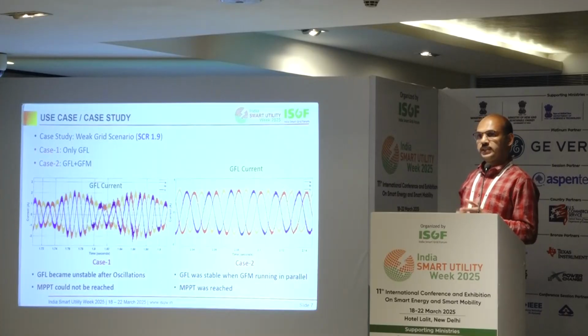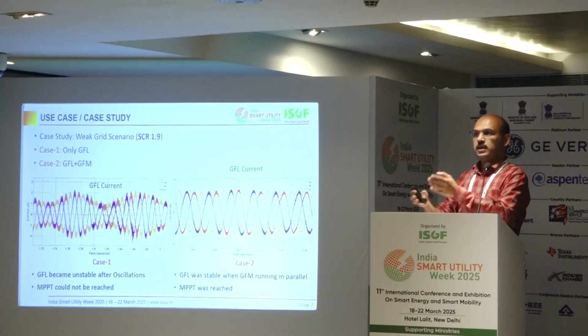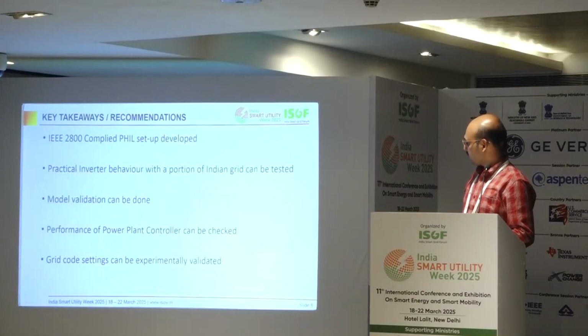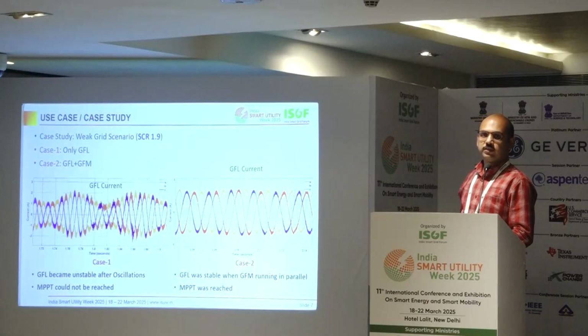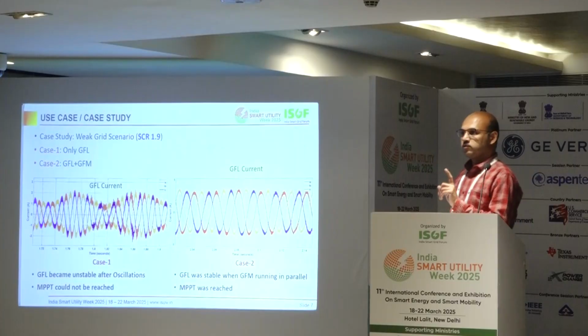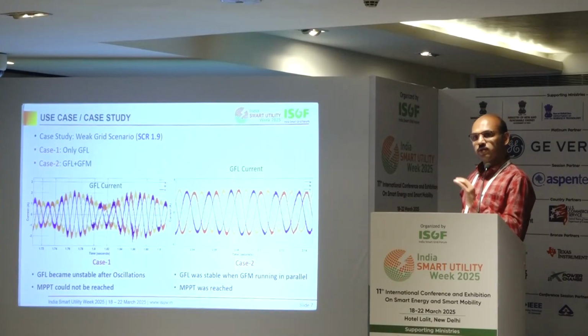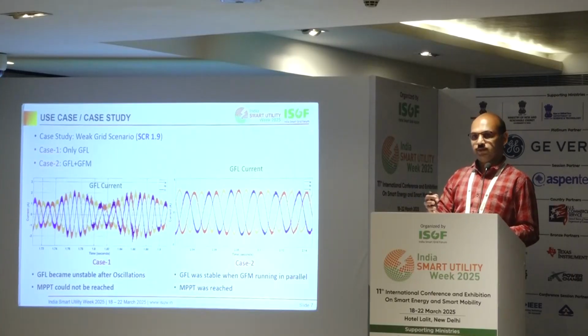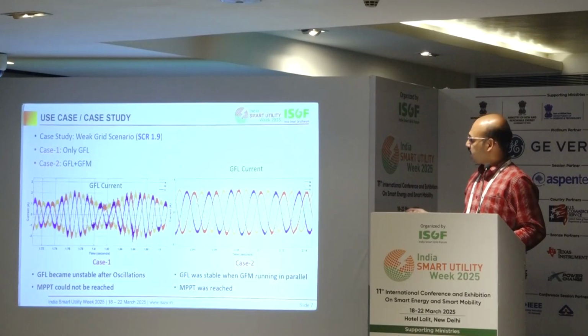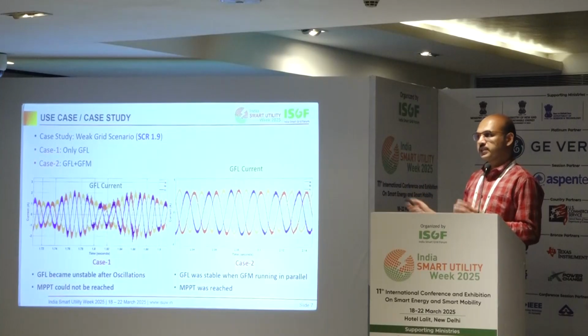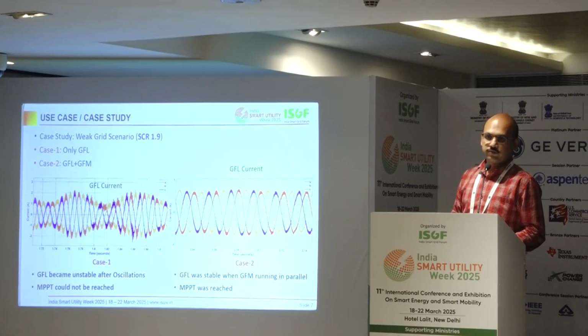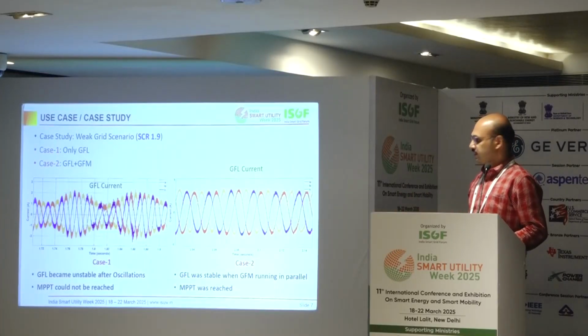When I am putting GFM in parallel with GFL for the same SCR, this is the GFL response - you can see no oscillations. So this gives an interesting insight: whenever you have very low SCR, like below 5, if you can operate a GFM in parallel with your GFL, then GFL will work fine. So maybe for future weak grid scenarios this can be adopted. We are studying this more, but it's a very interesting result which can have a far-reaching impact.